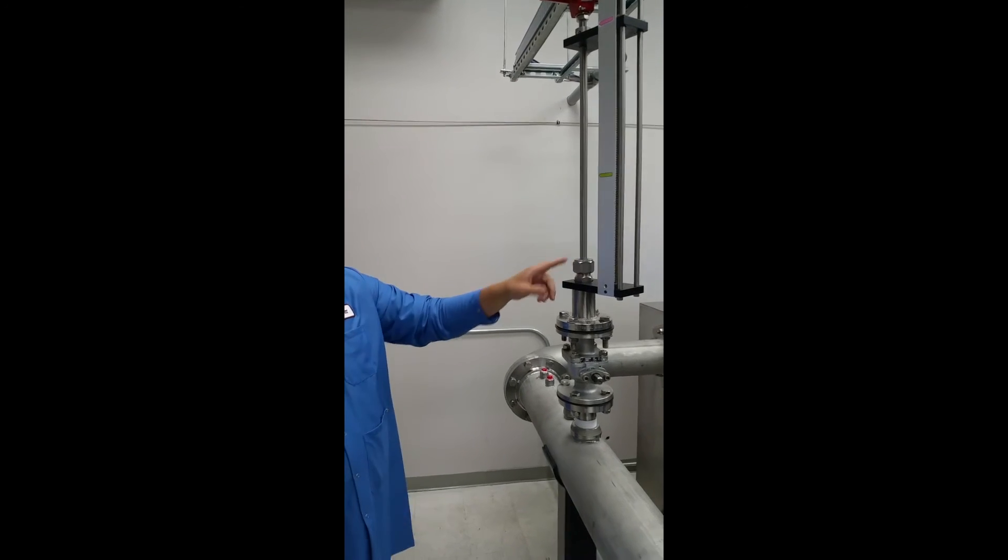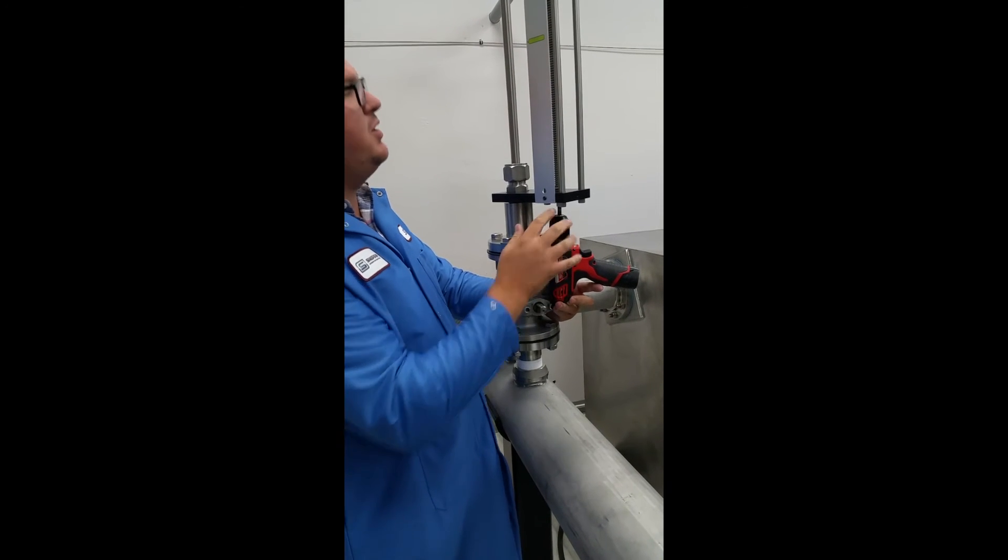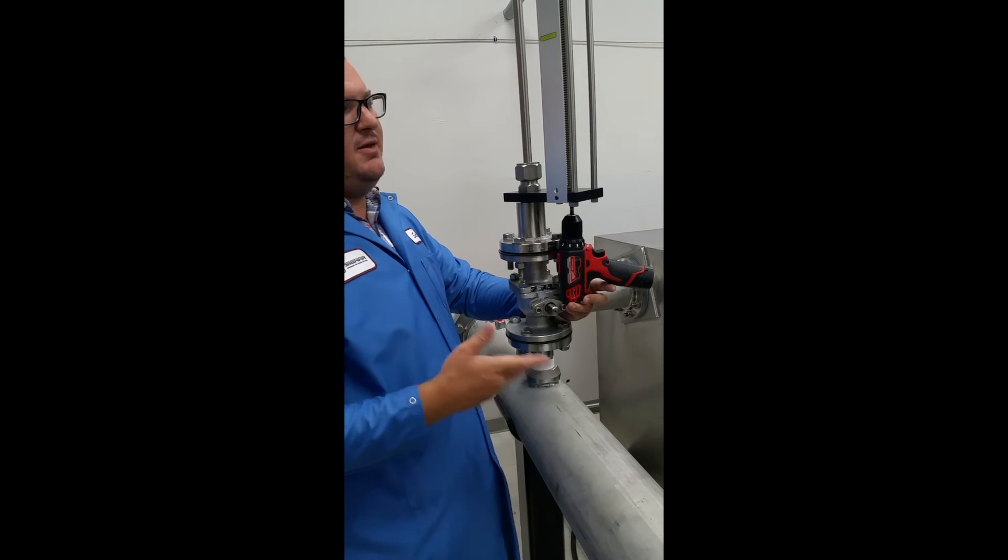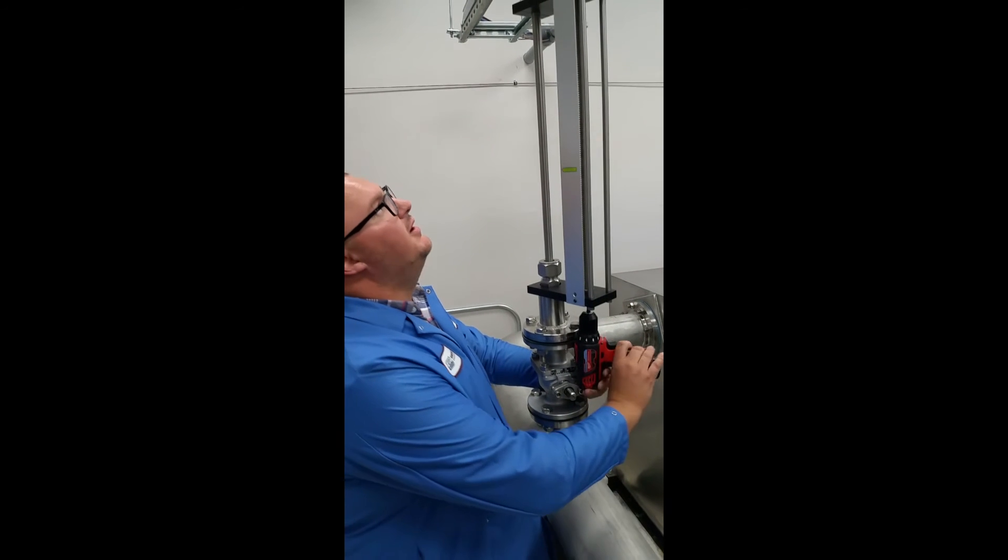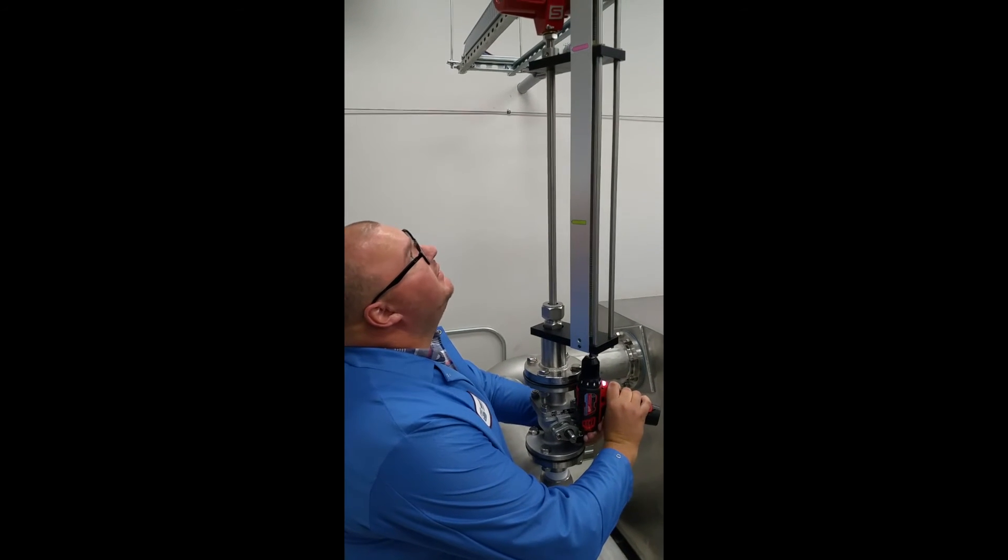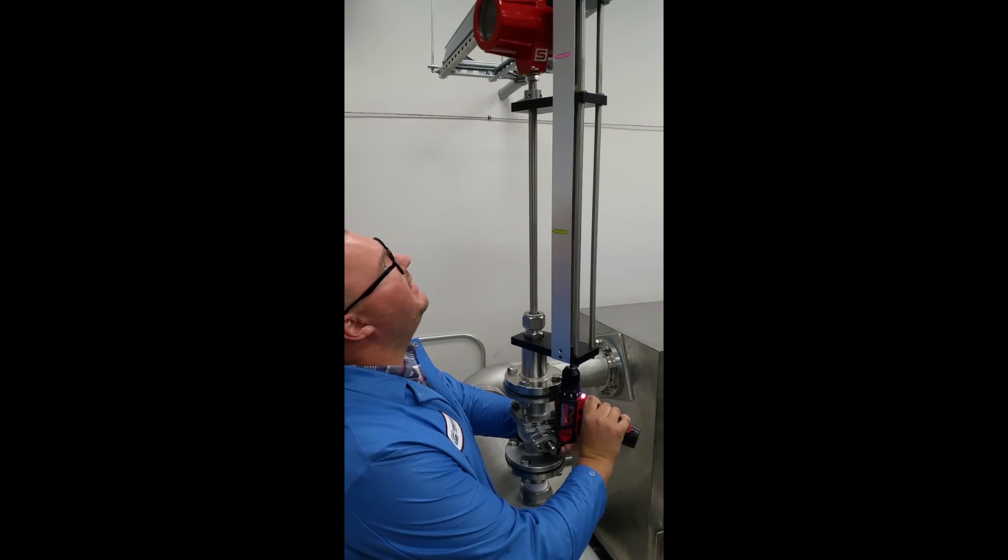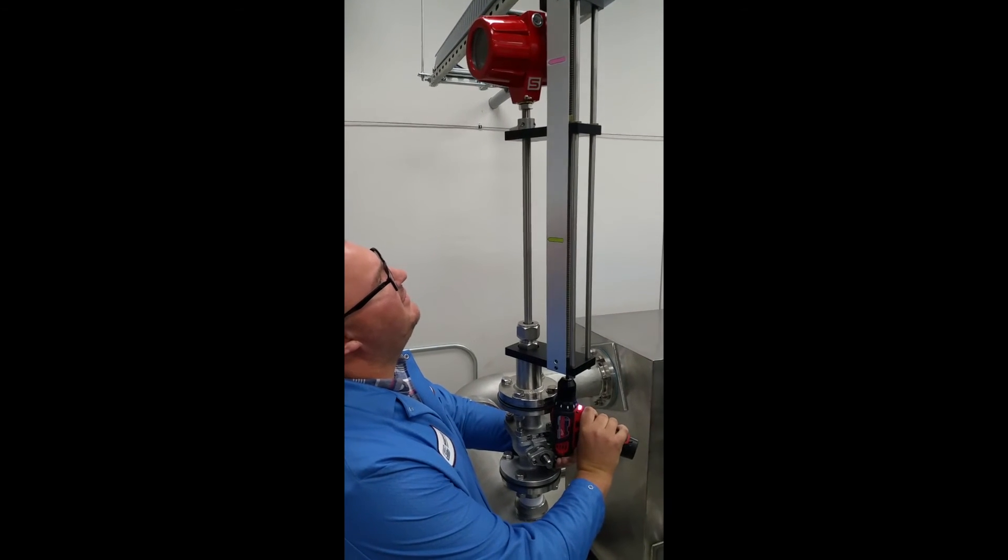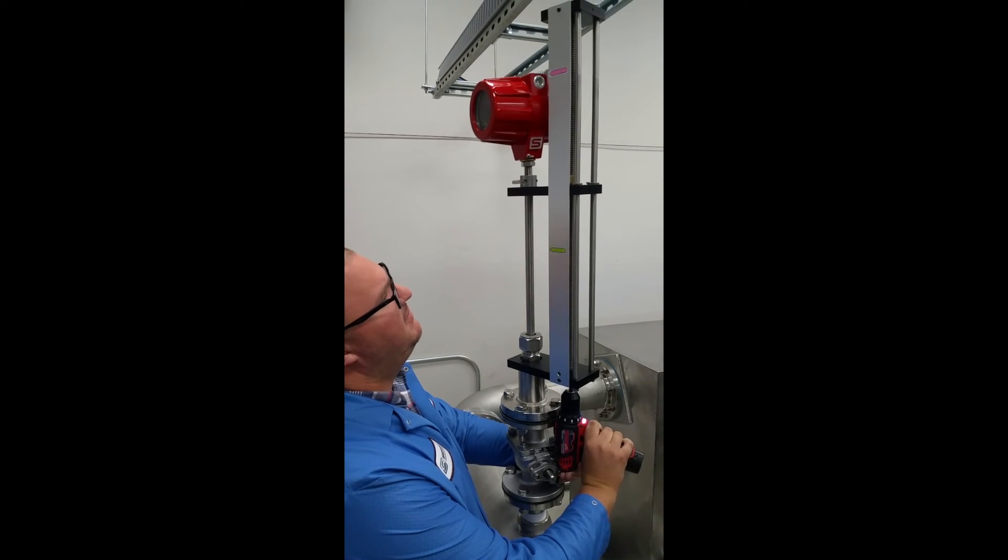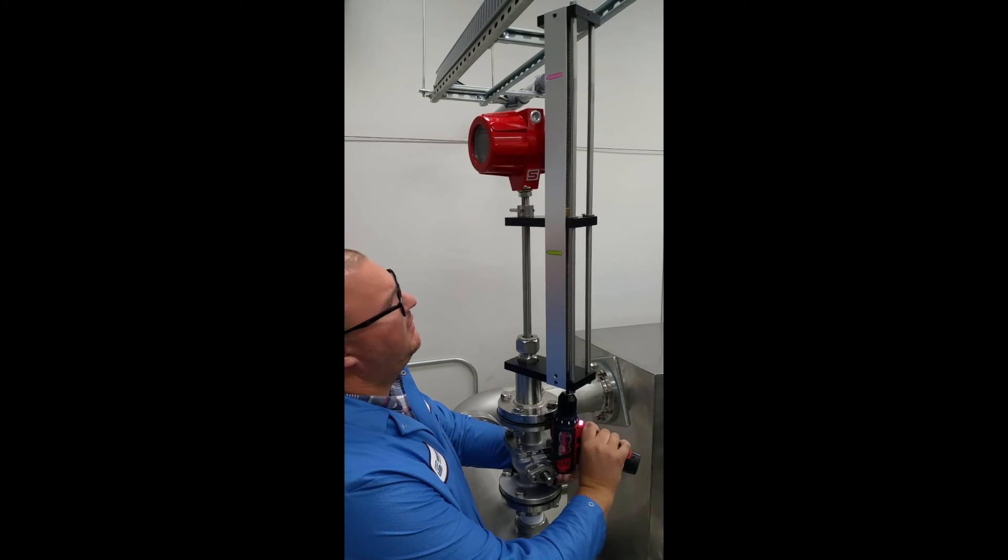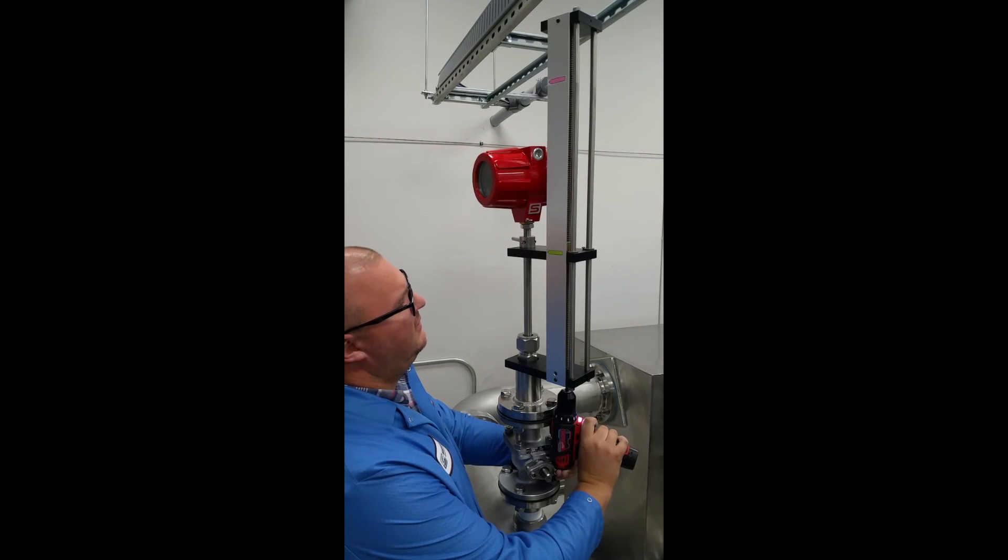Now I'm ready to actuate our retractor. I've got my power drill here. Quarter-inch ratchet adapter. Depending on the pressure of your system, you might have to use a different tool or a more heavy-duty tool to actuate it. And I'm just going to slowly lower it. I'm going to be watching the top bracket. And when it gets to my green mark there, I'm ready to stop. And my probe, I'm getting my probe in the middle of the pipe. There we go.